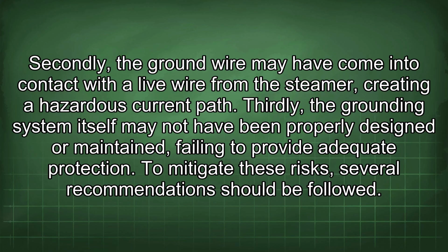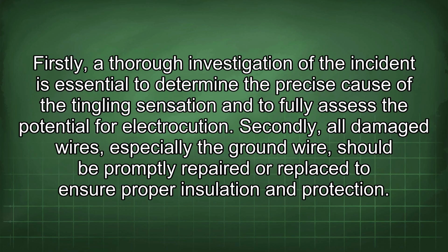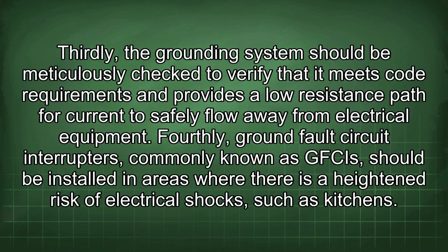To mitigate these risks, several recommendations should be followed. Firstly, a thorough investigation of the incident is essential to determine the precise cause of the tingling sensation and to fully assess the potential for electrocution. Secondly, all damaged wires, especially the ground wire, should be promptly repaired or replaced to ensure proper insulation and protection. Thirdly, the grounding system should be meticulously checked to verify that it meets code requirements and provides a low resistance path for current to safely flow away from electrical equipment.